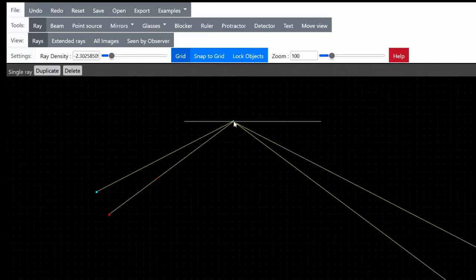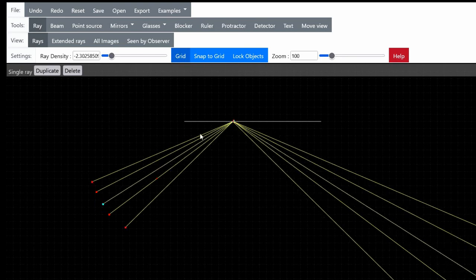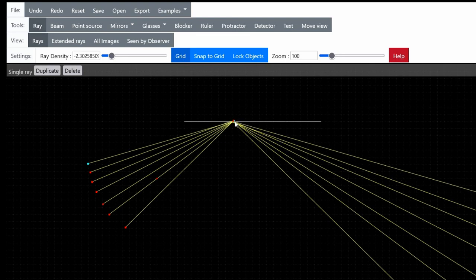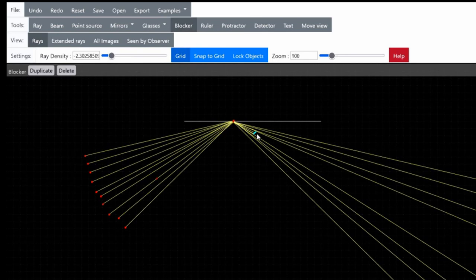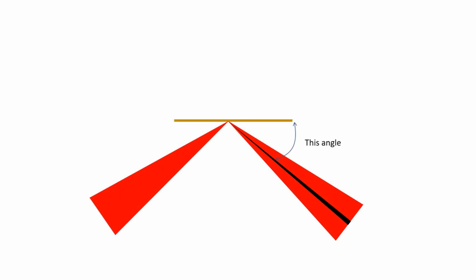If you have a very thin gold coat on a piece of glass, it will act like a mirror. If you shine a laser at that mirror, it will be reflected. But a very thin gold mirror has a funny property: at one specific angle, the light doesn't get reflected — it gets absorbed and disappears. This is an interesting property of the optical physics of photons and metals, but for our purposes it's enough to know that this thing happens. There's an angle, and we can build an instrument to measure it. Depending on what's right next to the gold mirror — the next molecule over from the gold — the angle will change. If the gold is in air, you get one angle. If you immerse it in water, a different angle. If you put it in sugar water or alcohol, you get more angles again. Anything that changes the molecules stuck to the gold will change the angle the instrument measures. So this angle gives you a kind of ruler — it lets you measure how much stuff is bound to that gold surface.